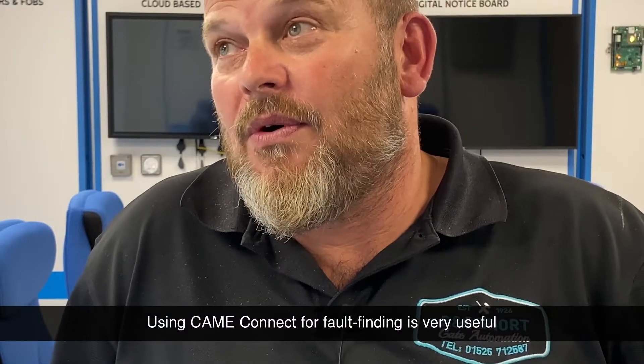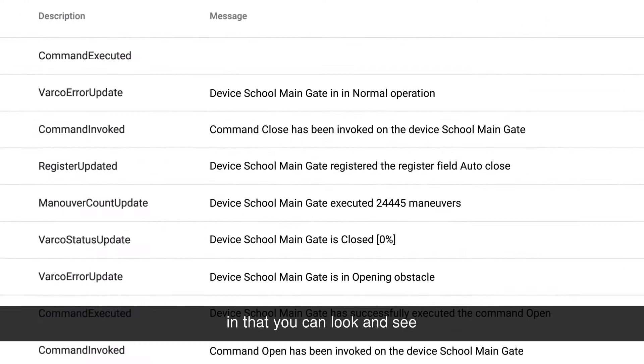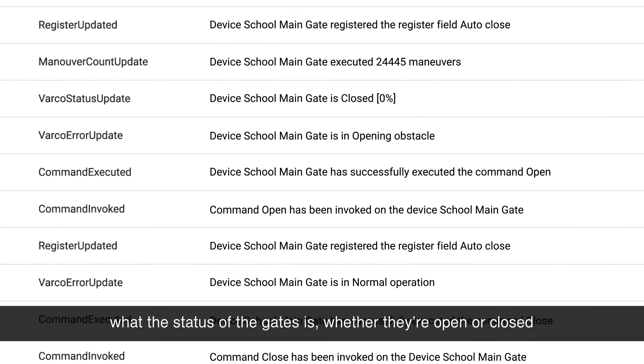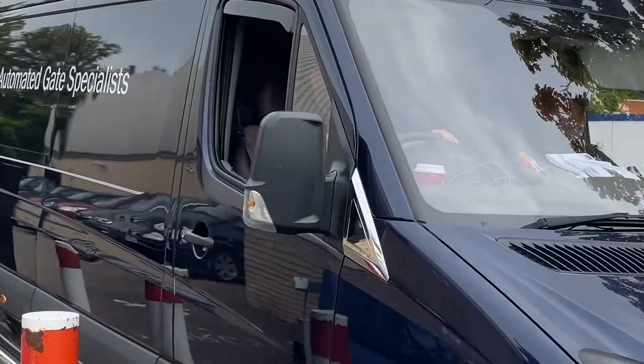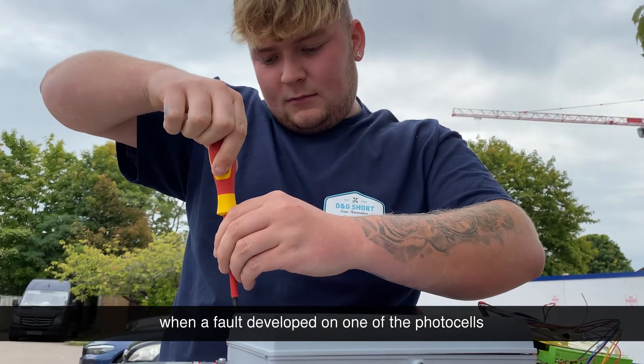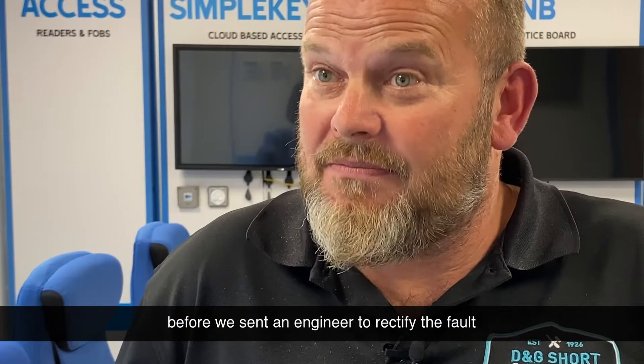Using CAME Connect for fault finding is very useful. The data that's given back is very useful in that you can look and see what the safeties are doing, what the status of the gates is — whether they're open or closed — and also any faults that might have occurred with encoders and such like. We've got an installation in Exmoor, which is quite a distance from us — we're based in Bedfordshire — and it was useful to have CAME Connect when a fault developed on one of the photo cells, allowing us to diagnose it before we sent an engineer to rectify the fault.